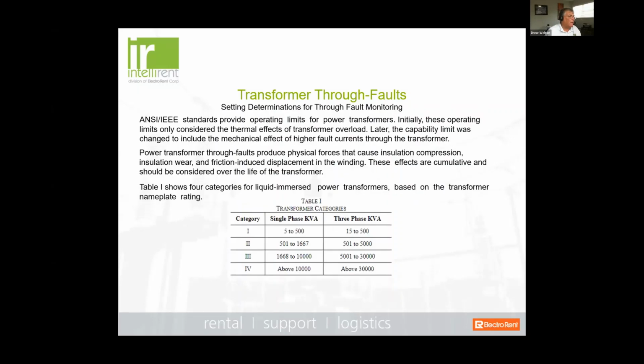Now, how do we know when that's damaging? How do we set a through fault monitor? First of all, we have to determine what category the transformer falls in. Categories 1 through 4 basically have to do with the kVA rating, both single and three phase. So it would be set a little differently based on the type of transformer and its category. But again, it's important to know that through faults will produce physical forces that cause insulation compression, insulation wear, and friction-induced displacement in the windings. These effects can be cumulative and should be considered over the life of the transformer.